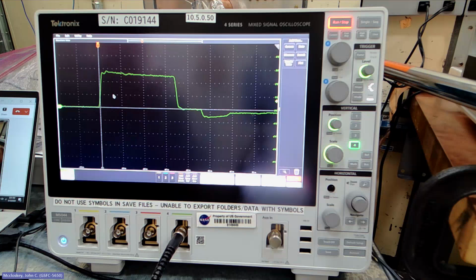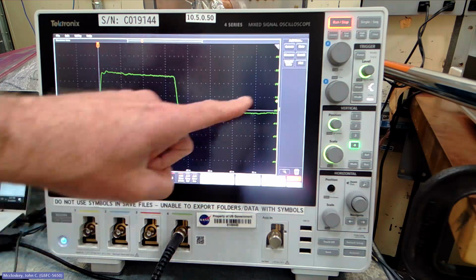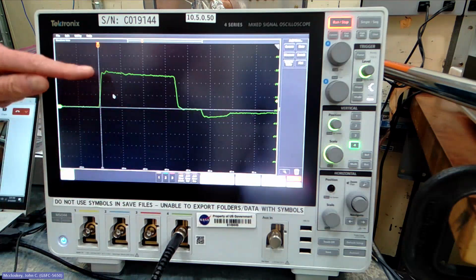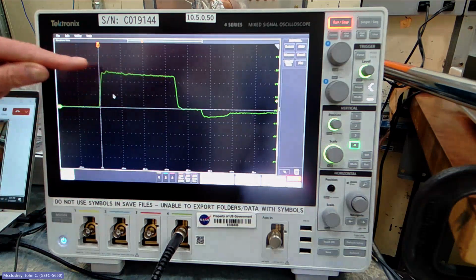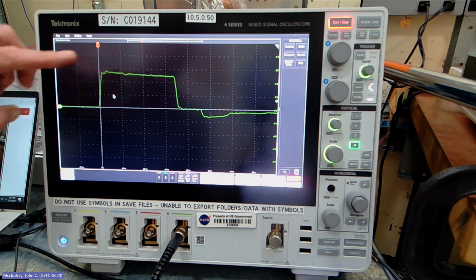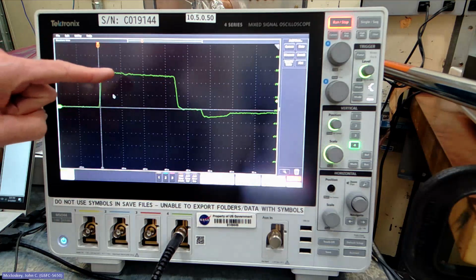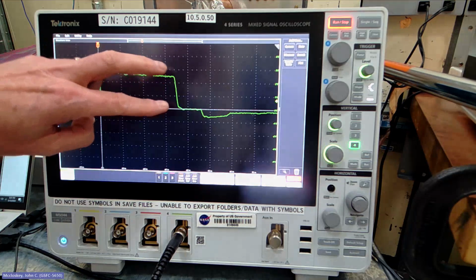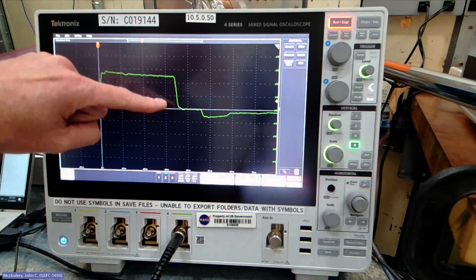And as we said, that's 5 amps into 50 ohms, 250 volts, divided by 100 through the 40 dB of attenuation. So 2.5 volts. So 1 volt per division. We're sitting here right around 2.5 volts. You're getting a little bit of sag on the top part of the waveform. So I've adjusted it so that I'm at least getting a full 2.5 volts on this falling edge.